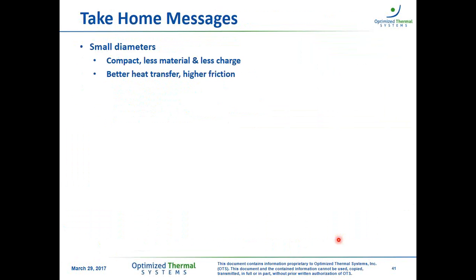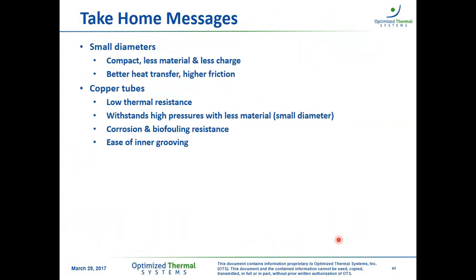So the take-home messages include small diameters. They are more compact, they require less material, and they will lead to less refrigerant charge. They will yield much better heat transfer coefficient, though with higher friction factor. Copper tubes have low thermal resistance. They can withstand high pressures with less material. They have some additional benefits that might not necessarily be used in every design, such as corrosion and biofouling resistance, and enhancing the copper tubes with internal grooving is pretty much straightforward.